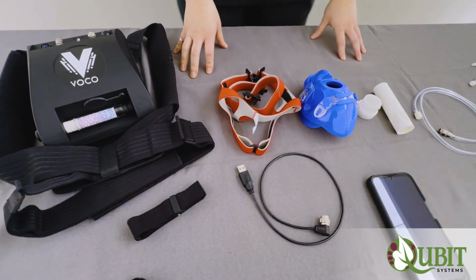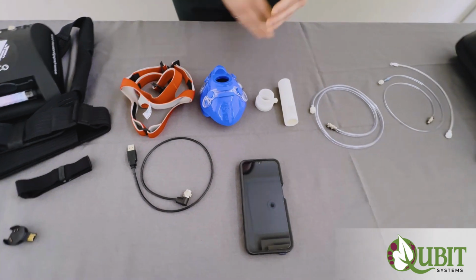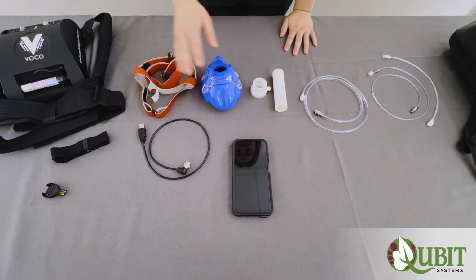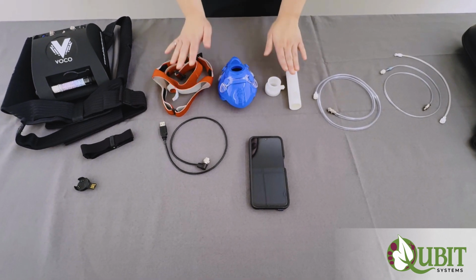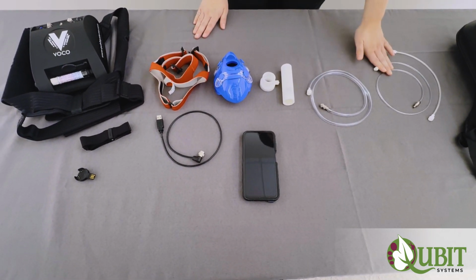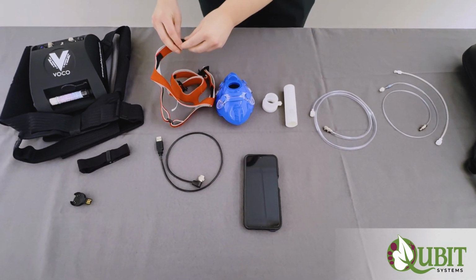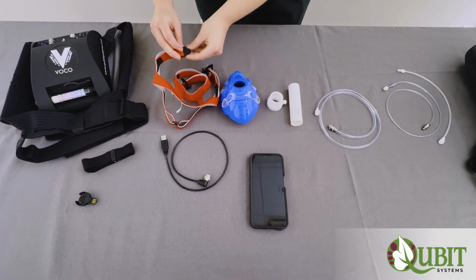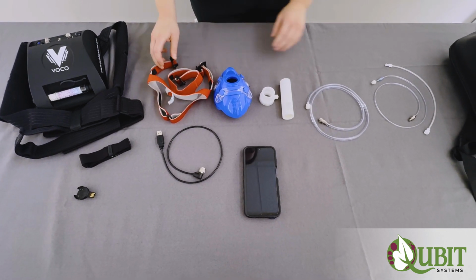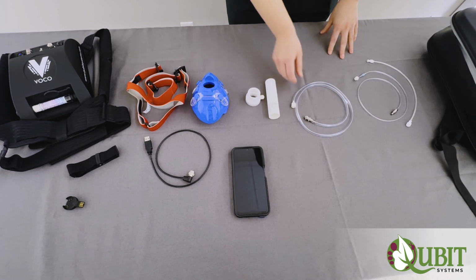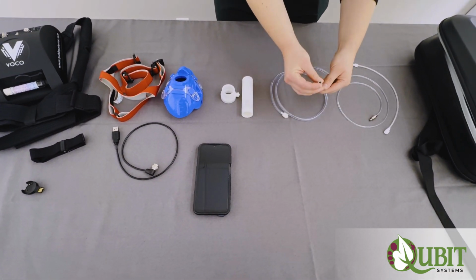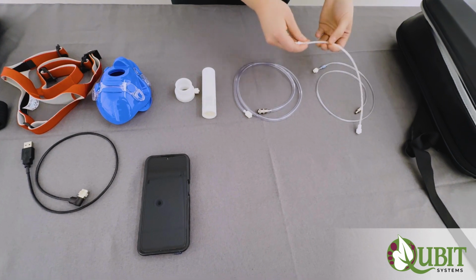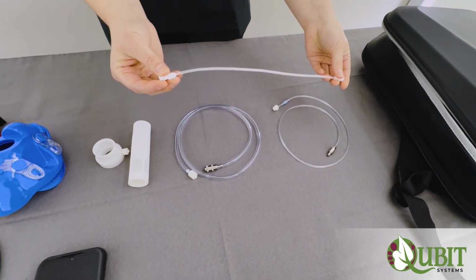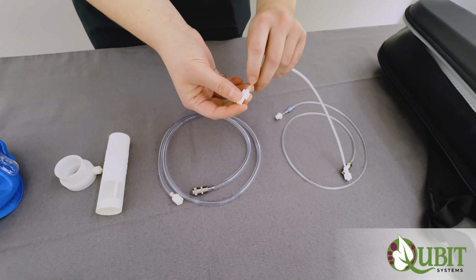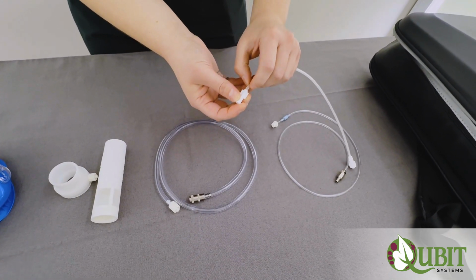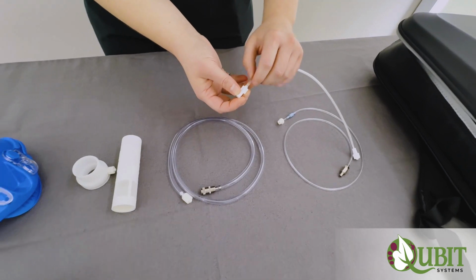Other simple checks to complete before a test: make sure all of the components are present, the mask, the headgear, the adapter, the PTAC tube, the gas tube, and the Nafion, and then making sure the components are all stable, not broken from lots and lots of use. And the tubing, this tubing is generally fairly stable. However, over many years of use, the Nafion does eventually wear away here. You want to make sure that your Nafion tube is still in good condition before you begin a test.